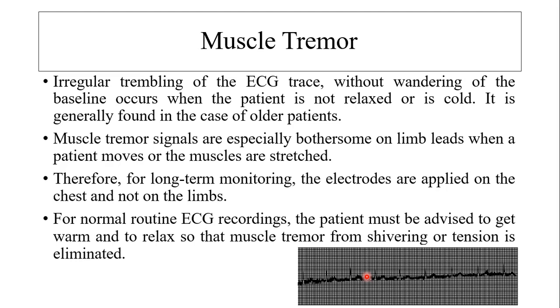For a normal routine ECG recording, the patient must be advised to get warm and to relax so that the muscles can be relaxed and not shivering, so that this artifact may be eliminated.